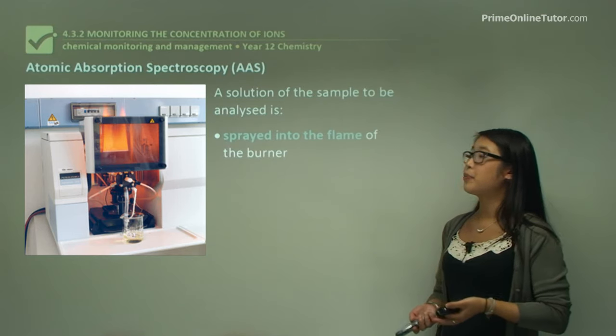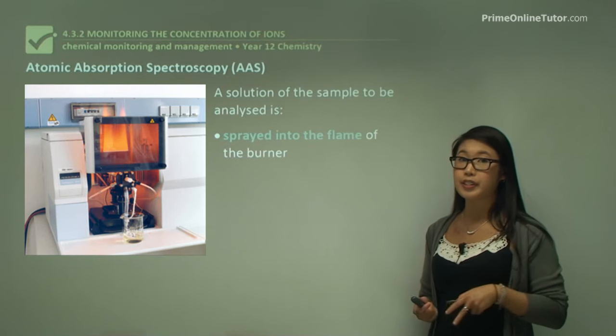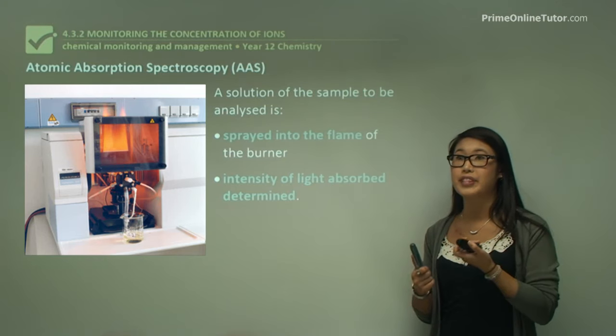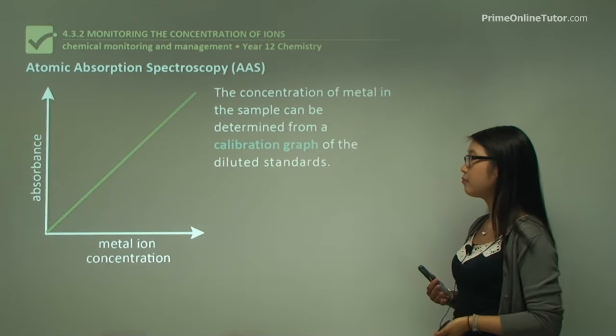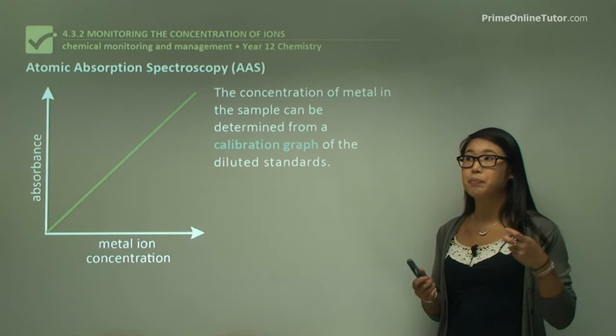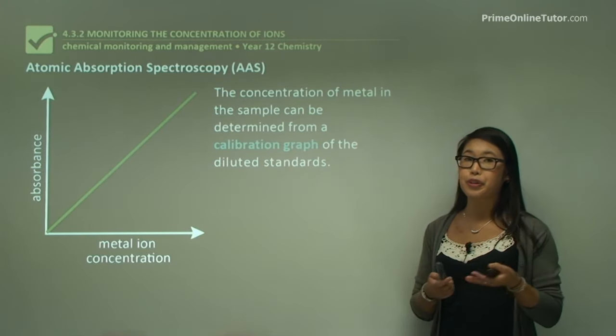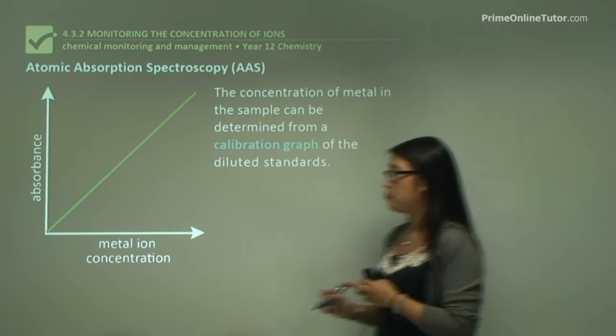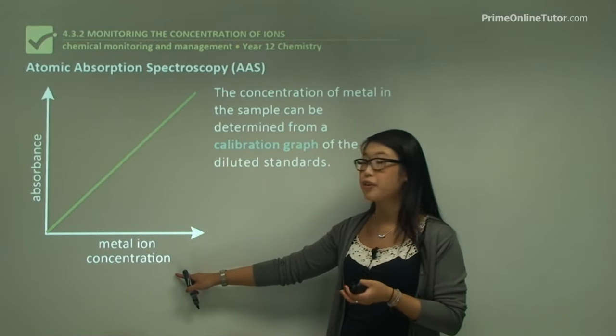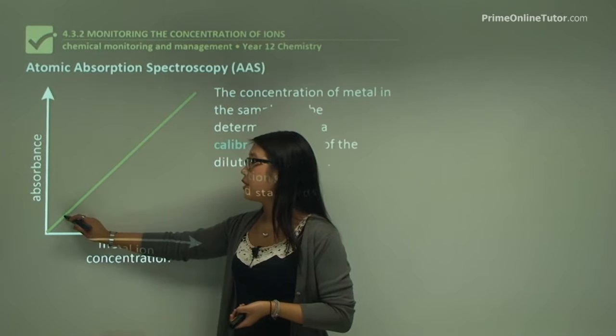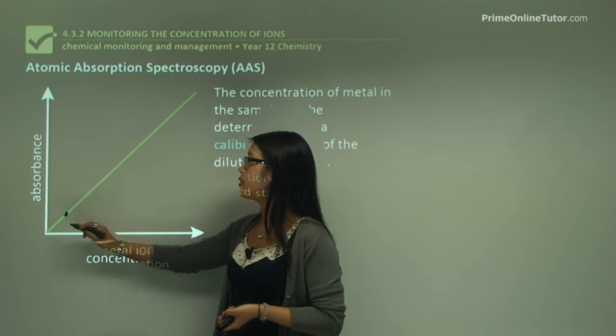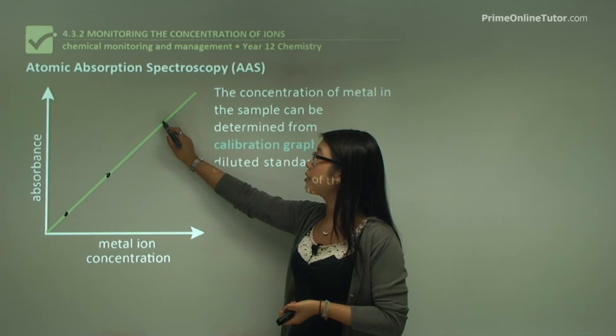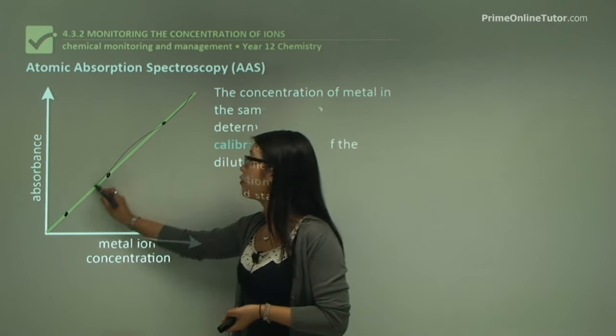The solution of the sample is sprayed into the flame of the burner, and we look at the intensity of light absorbed to determine how much of the ions we're looking for are present. We first make up a set of standard solutions of known concentrations and analyze them each separately in the AAS machine. We plot a graph of absorbance against concentration of metal ions. At each concentration, we get a corresponding absorbance value, and from these points we make a calibration curve.